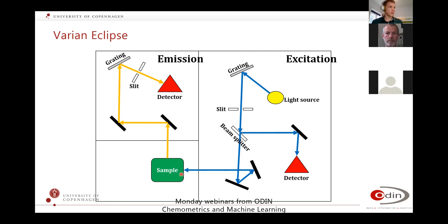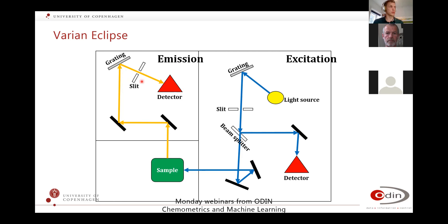The sample is in a 90-degree configuration, meaning the light comes in and you're measuring at a 90-degree angle to the sample. Then you have mirrors and a new grating, which decides what wavelengths you are actually measuring at your detector. These slits can be adjusted depending on how much light you want to get through and how precise you want to be.